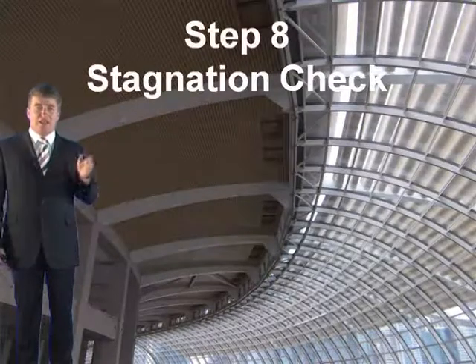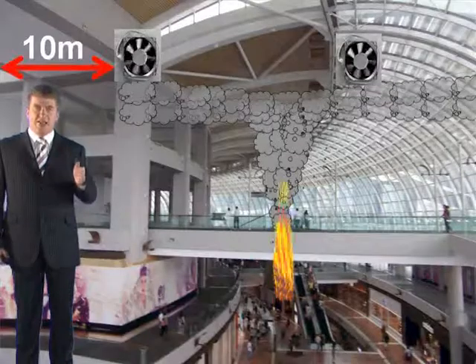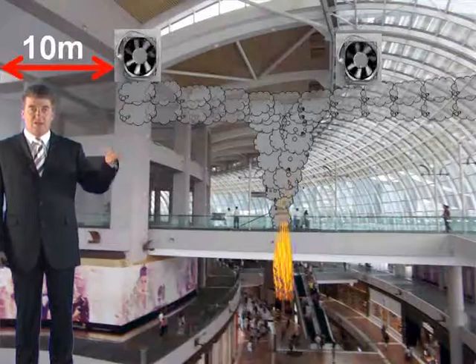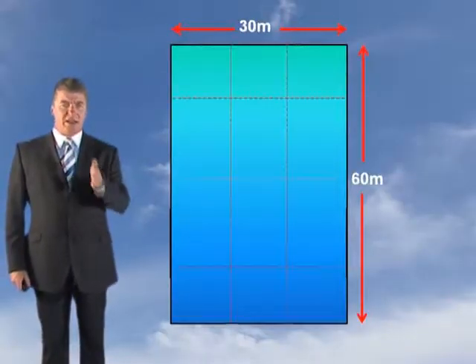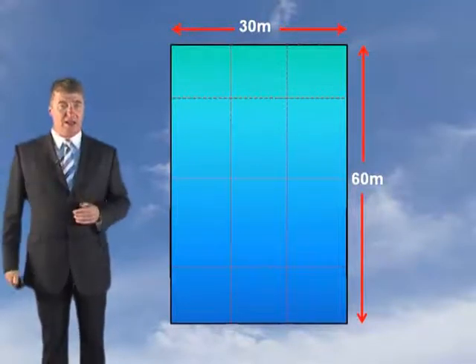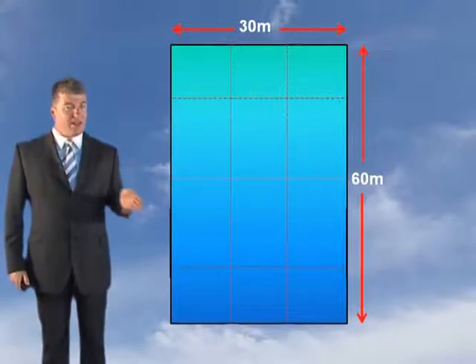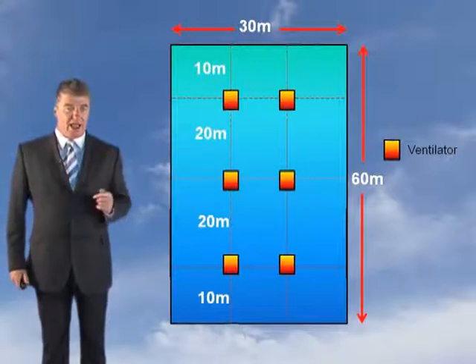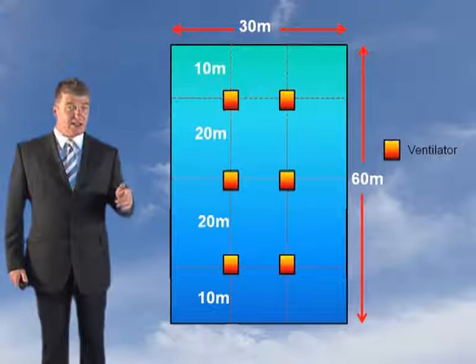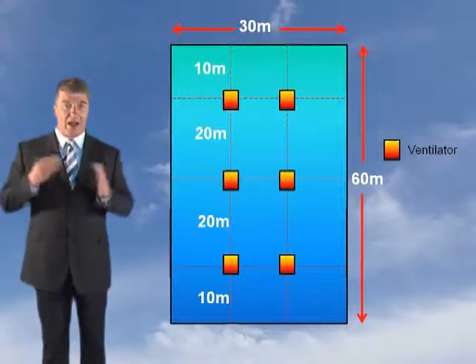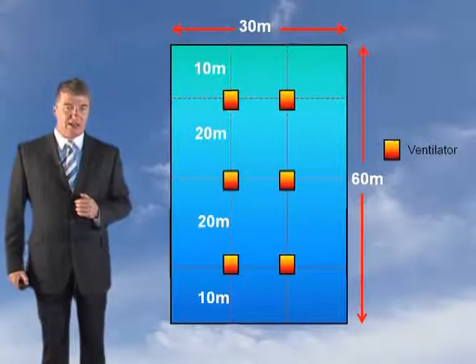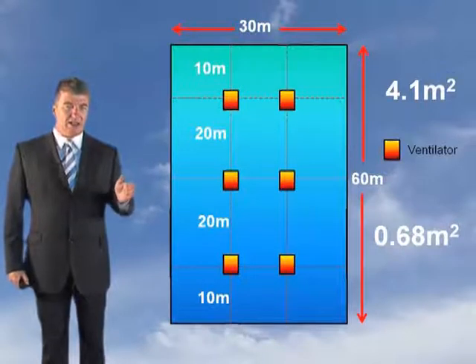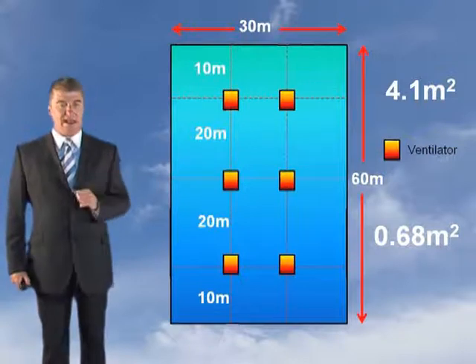Before deciding where to locate the two ventilators, you've got to carry out the stagnation check — step eight. This only applies to natural ventilation, and we are going for natural. The maximum distance from the edge of a building to a ventilator is 10 metres, and ventilators can't be more than 20 metres apart. You mark a line at 10 metres from the edge, ensuring no more than 20 metres between them, and wherever the lines intersect, you need a ventilator. As you can see, there are six intersections, so you need six ventilators. Although we only need two for size, we need six to meet the stagnation check.